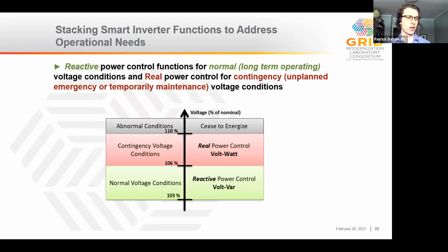I mentioned that these functions can be stacked, and this is an approach states are starting to take, and I think it's effective. Under normal voltage conditions, shown in green here, the volt var function is the primary response. Once voltages get above the acceptable range—and there are industry standards on what range utilities need to keep voltage within—if voltage starts to exceed that range, then this other function we just looked at, the volt watt, can be used to start backing off the power production.